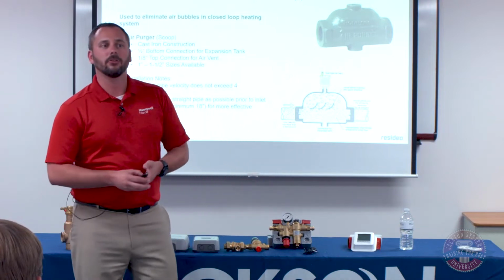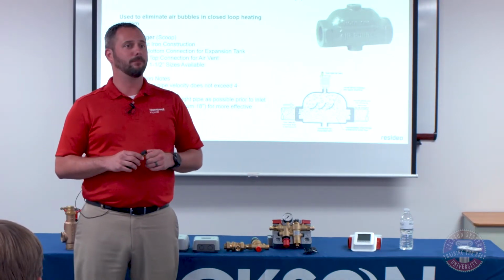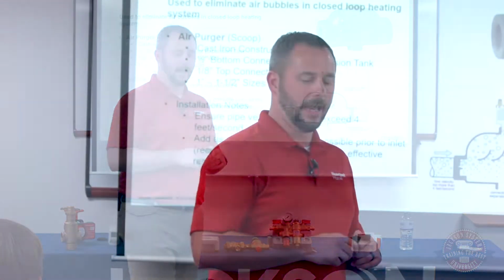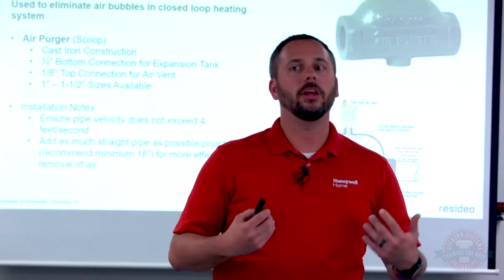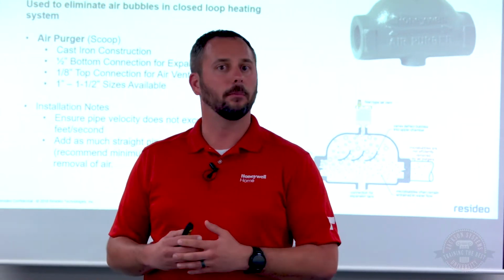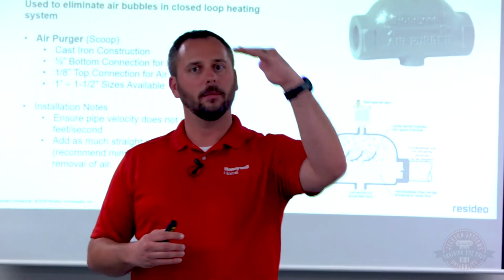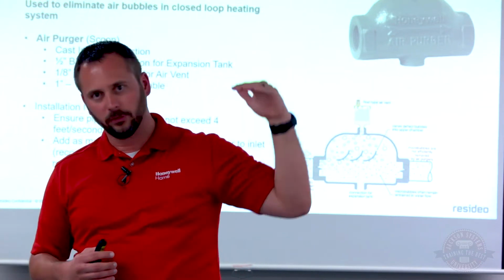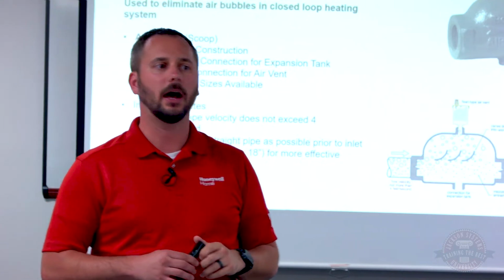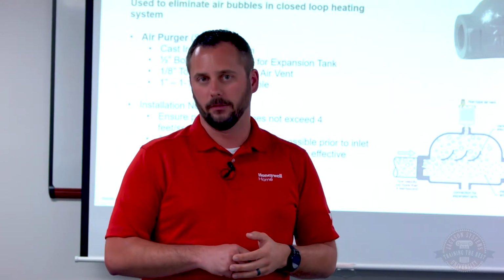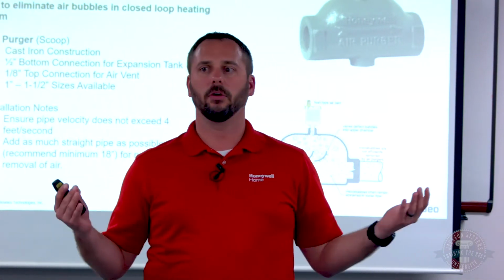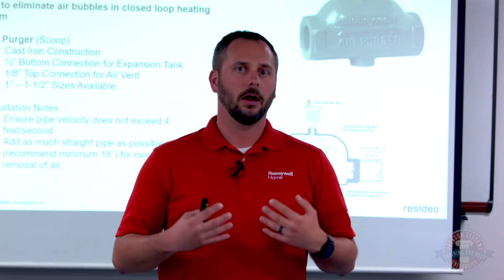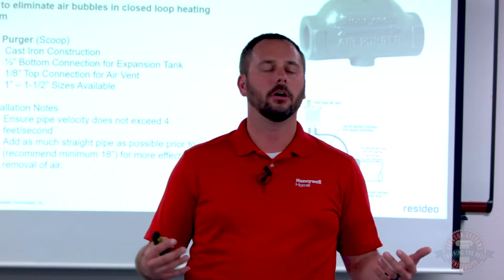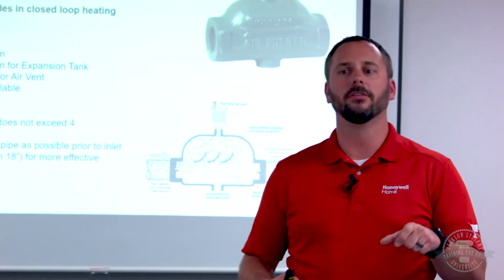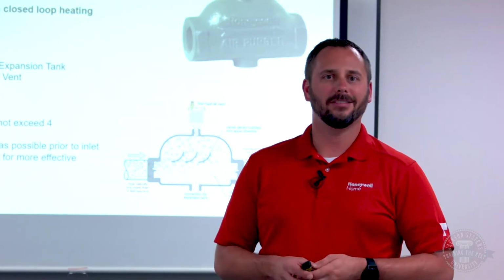The first, the air scoop, is really nothing more than a big block of cast iron that has a couple of vanes inside of it. The theory behind this is, as water travels through the piping, the air is going to collect and roll up to the top, because air floats. It gets caught in those vanes and then purges up through the top through an automatic air vent. These used to be the standard 20, 30 years ago. The reason was we sold cast iron boilers and copper fin boilers, essentially high-mass devices that had a lot of water and very big manifolds inside of the heat exchangers. Today, that's not exactly the case.